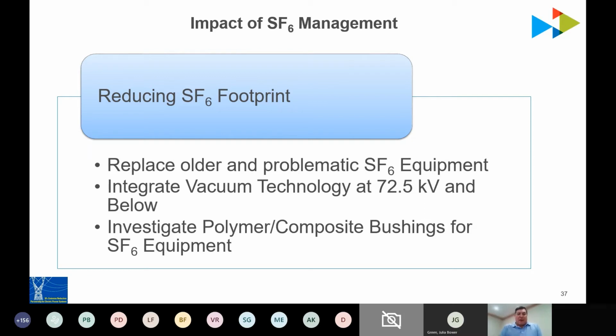We're also looking at polymer and composite bushings for SF6 and clean air vacuum equipment at Southern Company. We believe this makes the equipment a little lighter and easier to manage and transport. We see advantages with composite bushings creating better seals compared to porcelain bushings. You get a nicely machined, high-tolerance O-ring groove and O-ring, whereas with porcelain bushings the porcelain itself is the seat for the bushing, which may not be very well machined or manufactured. This could introduce leak points and cause the equipment to prematurely leak and require maintenance.